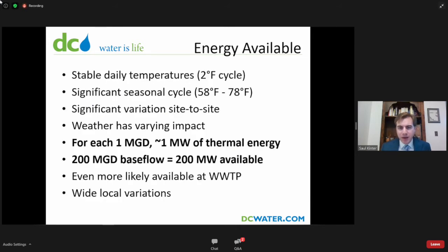So based on this, looking at about a 2-degree daily cycle and maybe a 20-degree seasonal cycle, what we found, if you do the calculation, is that for every 1 million gallons per day of flow, you have about 1 megawatt of available energy, assuming you can put a 10-degree delta T on the sewer, which should be about right. So in Washington, D.C., we'd have an average flow of about 300 million gallons per day on our wastewater system. And in terms of base flow, dry weather, overnight, accounting for some of the daily variation in flow, we can count on about 200 million gallons per day of that as pretty consistent, which means we're sitting on 200 megawatts of available thermal energy, which is quite a lot. It's just a big amount. It's enough to do maybe 100 buildings or more the size of our headquarters.